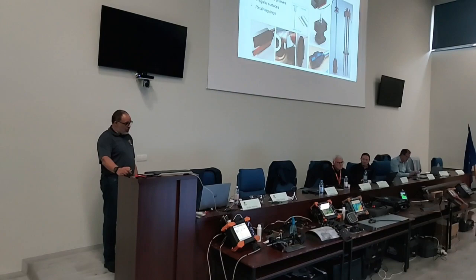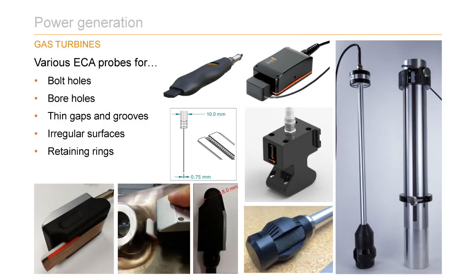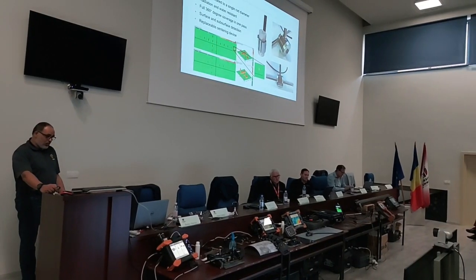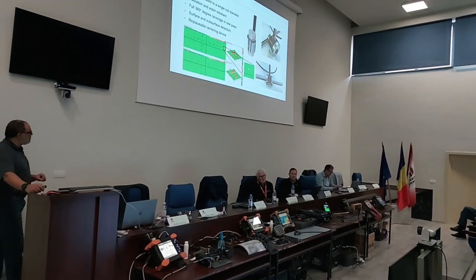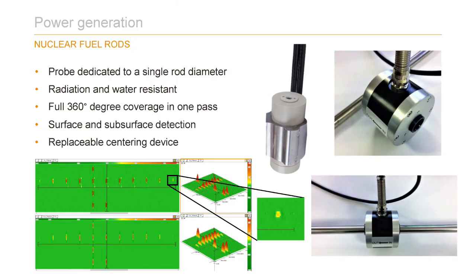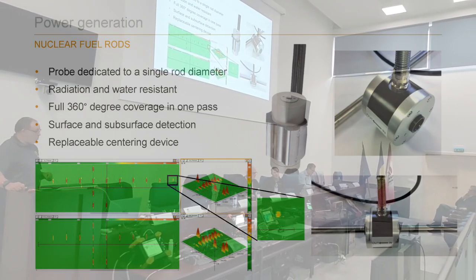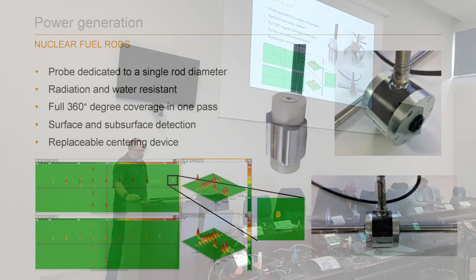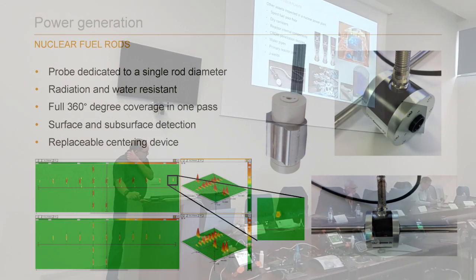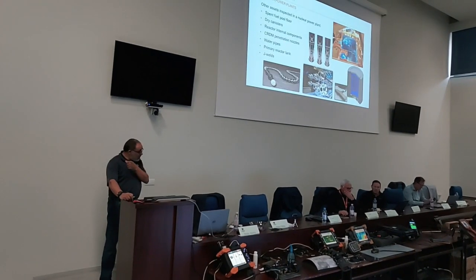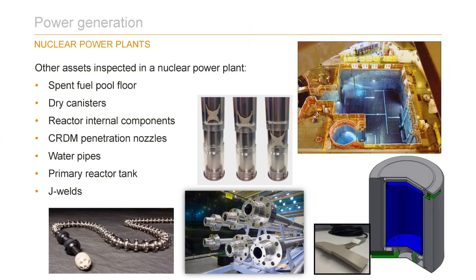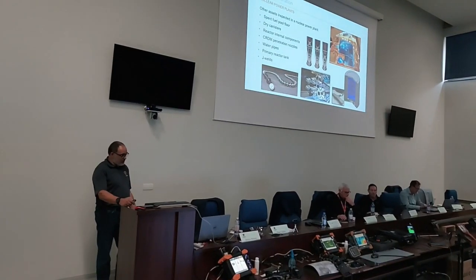Another type of probe, dedicated for groove for example, and boreholes. This one is a dedicated probe for nuclear fuel rods inspection. It's very important to keep those rods tight. You have uranium inside, high pressure also inside, so you don't want that to leak and contaminate your primary loop in the nuclear plant for example. So this is a dedicated probe for this inspection, and you can see a variety of dedicated probes, ultra flexible, can be very tiny to access a small space for example.